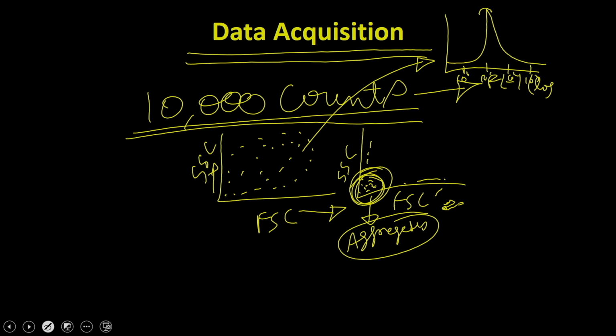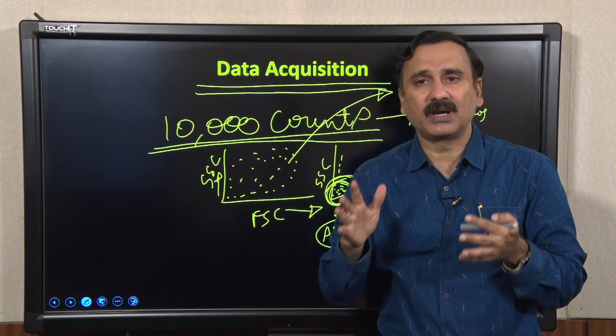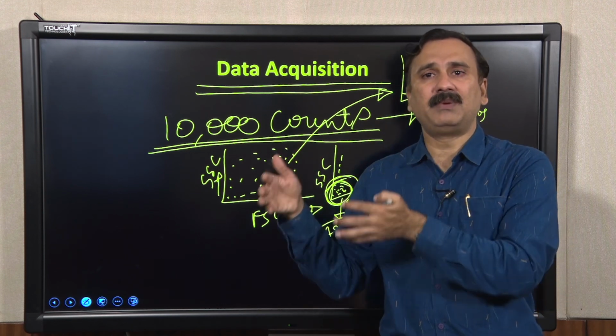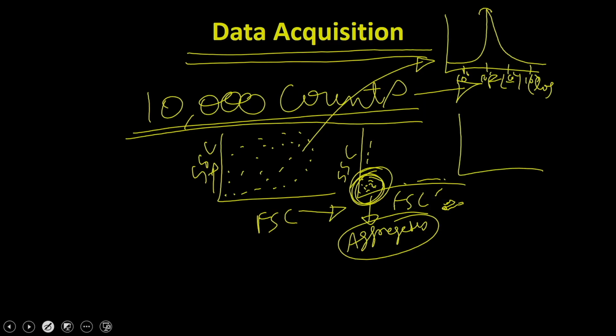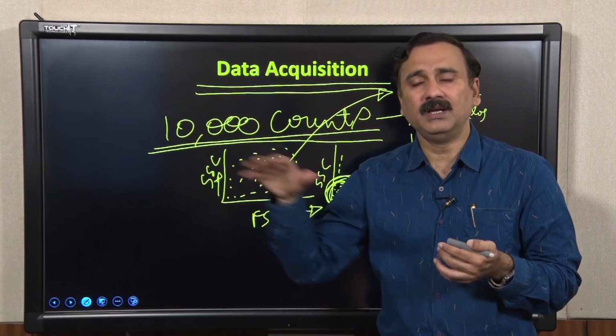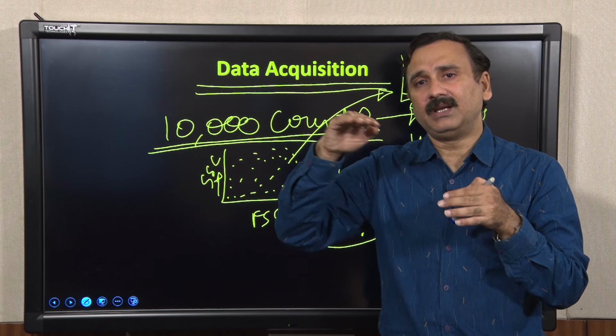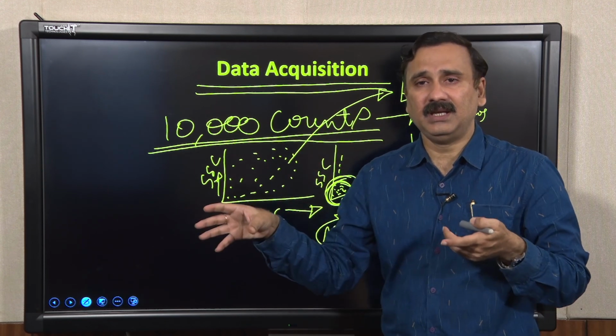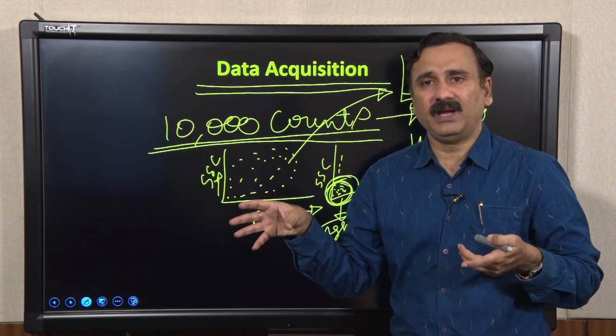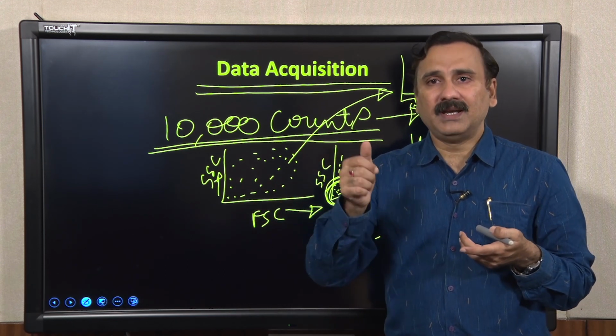Now, here you also have to consider that when you are looking at the histogram plot of unlabeled samples, an unlabeled sample is going to have a very low level of fluorescence, so it is always going to be like this. But you have the flexibility in a flow cytometer to increase the current as well as the gain of the instrument. What is meant by the current and the gain is that it is a virtual way of giving more intensity to the sample.